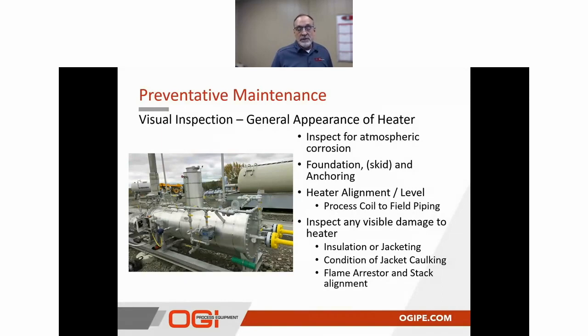Are the foundations displaced due to frost heaving or sinking, or is the process coil tied to field piping? Does it have any apparent stress on the process coil connections caused by field piping, or maybe the settling of the heater and its foundation? And then we're going to do some visual inspections for damage of the heater's insulation and jacketing, making sure that the condition of the jacket caulking is good. It's not cracked. If it is, obviously repair it.